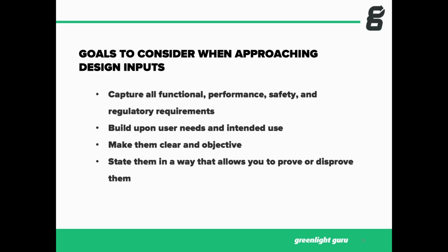For some types of products and in some markets, like the US or even outside the US, there might be standards or guidance documents that are specific and relevant to your product. Those standards and guidance documents may have criteria that you need to factor in as part of the design and development process, and you may need to capture those as design inputs. So understand that as soon as you possibly can.